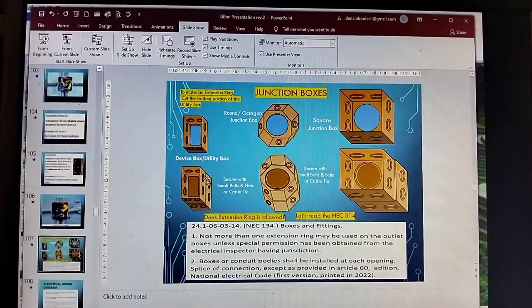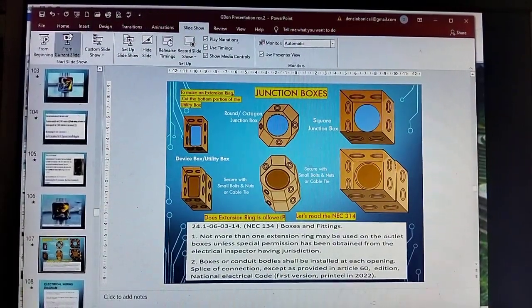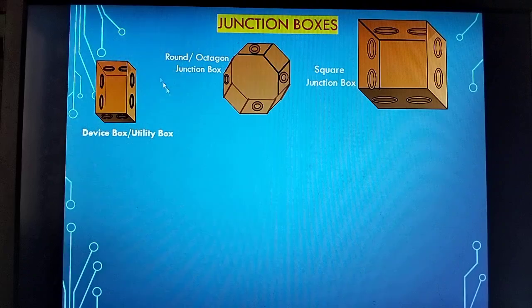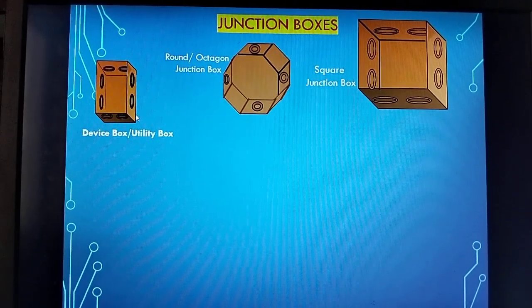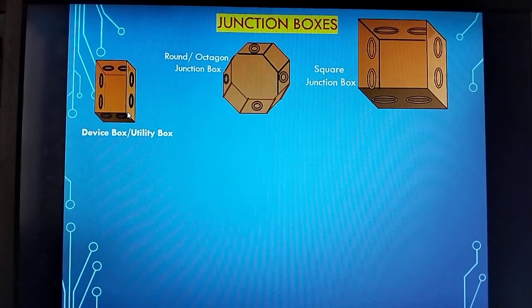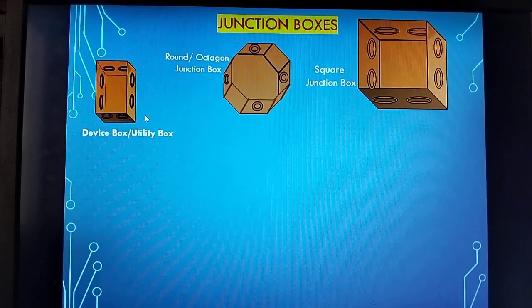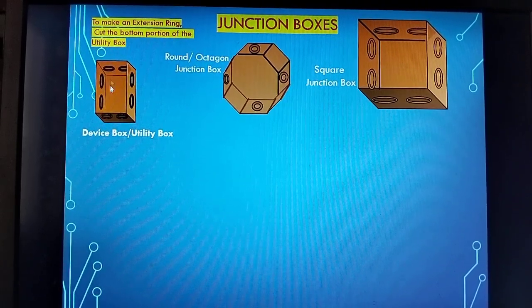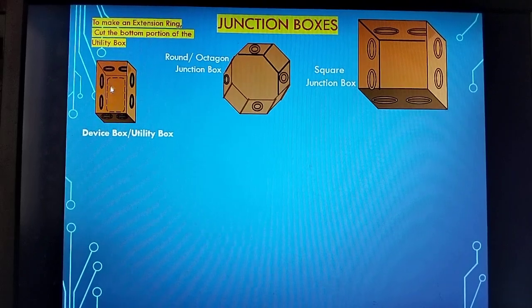To prevent violation, you have to add an extension ring, a box like this one. This is if you are going to utilize a utility box or device box and it is not enough for the lighting outlet, then you cut this portion.